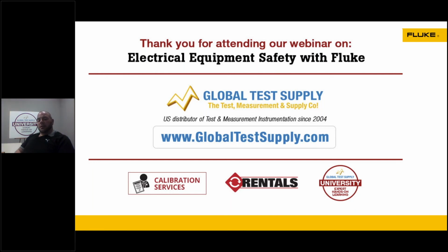Speaking of leads, it's a question our team gets relatively often. Will a fused test lead increase the category for the lead itself or for the instrument being used? No. Theoretically, your test leads and your meter are going to be pretty much matched. With Fluke, our test leads are category 3 1000 volt, category 4 600 volt, but even though your test lead could handle that potential energy, your meter couldn't. So it's not going to save your meter.